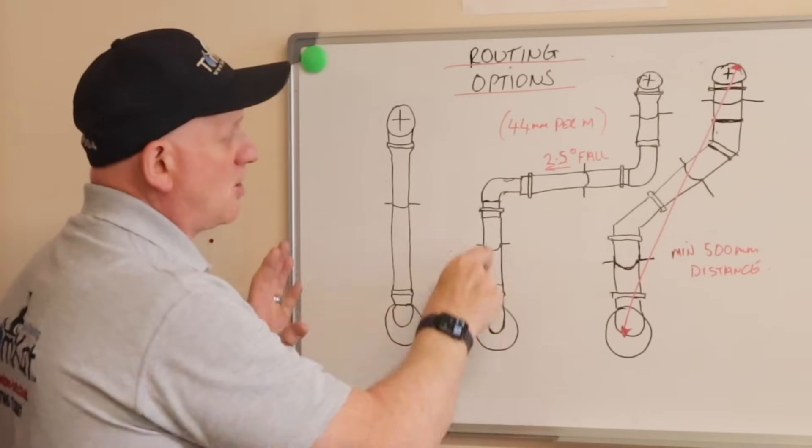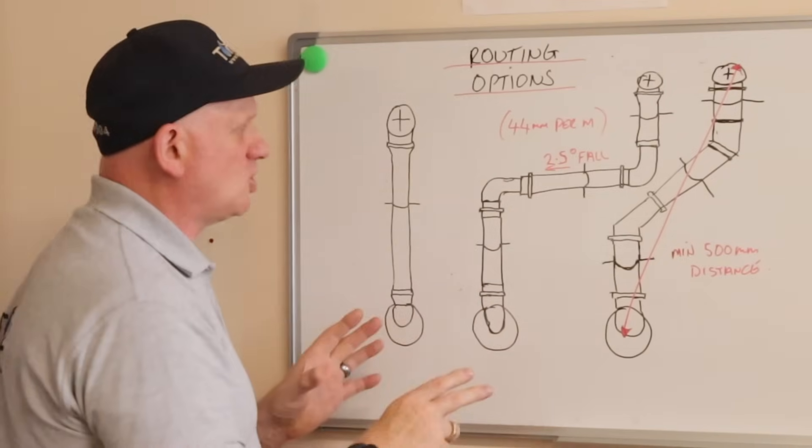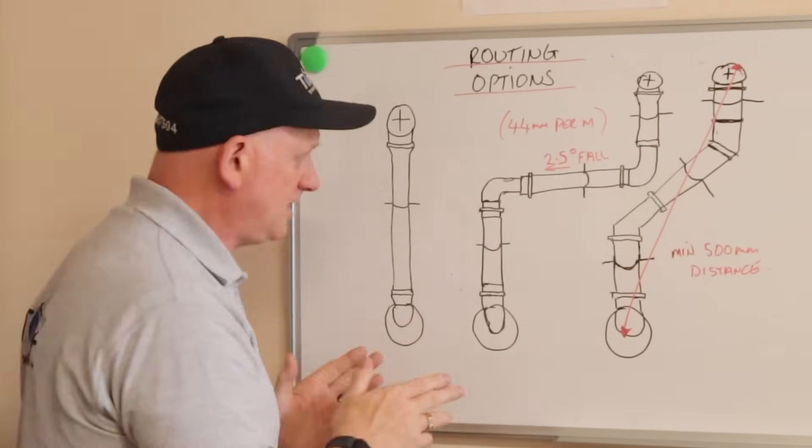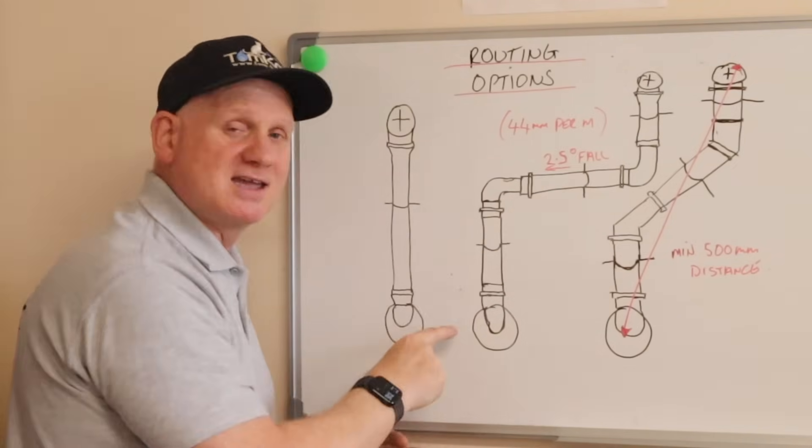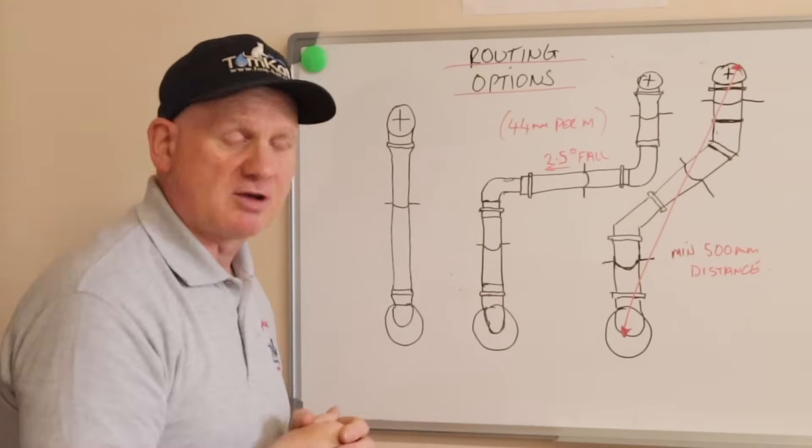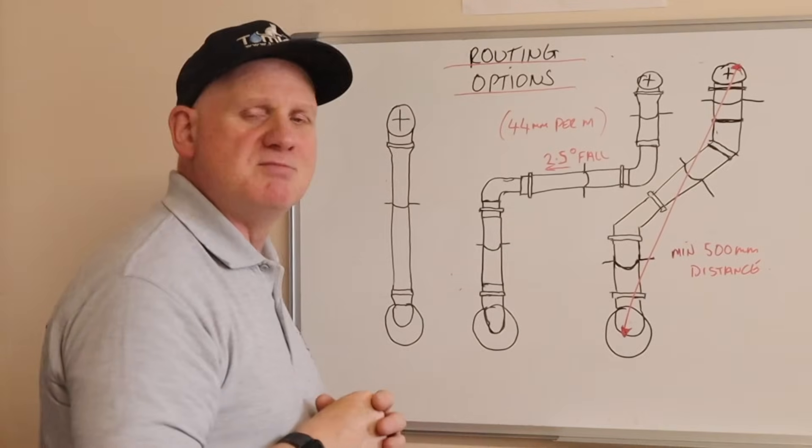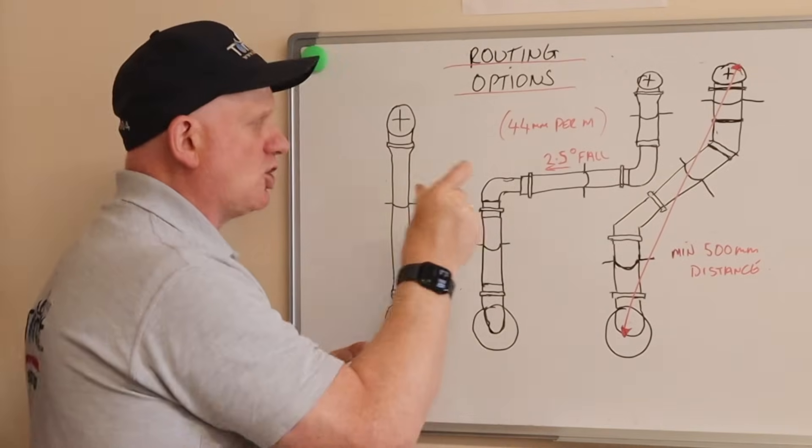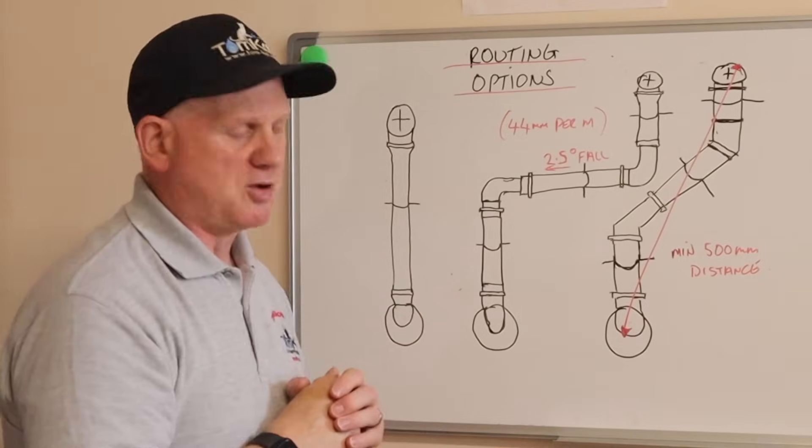So, when we go up and straight across and up again, we need to make sure we have a fall in the flue, and this is so the condensate can go back into the boiler, into the heat exchanger, and then out through the condensate trap and drain. We need a minimum of 44mm per metre, or 2.5 degrees, fall back to the boiler.